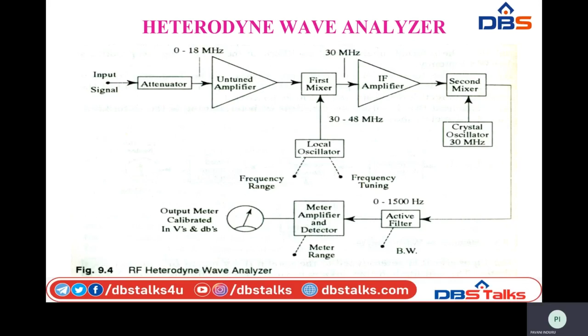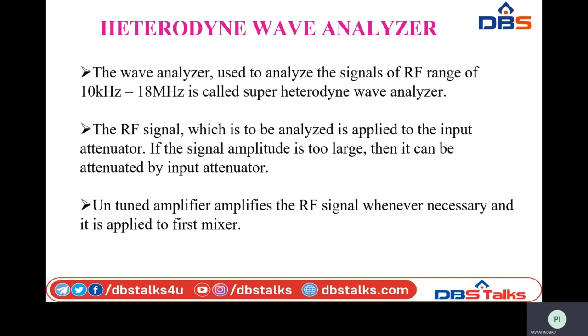Okay, so this is how the wave analyzer is used to analyze signals in the RF range, that is something about 10 kilohertz to 18 megahertz. So here the RF signal to be analyzed is applied to the input attenuator. If the amplitude is too large, it can be brought down, and then the untuned amplifier amplifies the radio frequency signal, and then it is applied to the first mixer. So here the frequencies which are beat together are in the range of 0 to 18 megahertz and 30 to 48 megahertz.